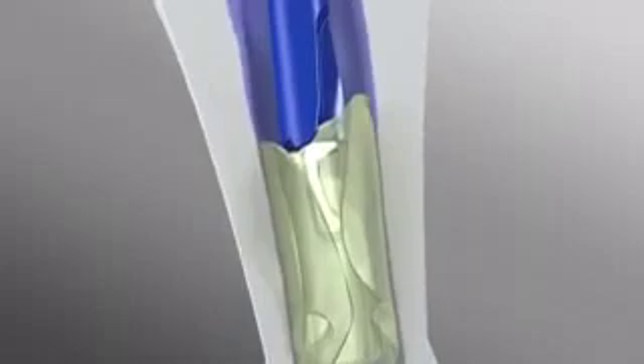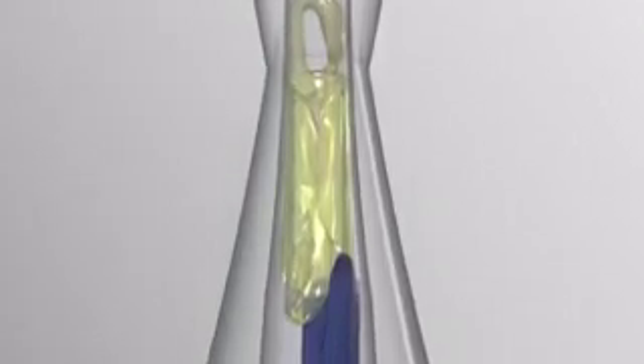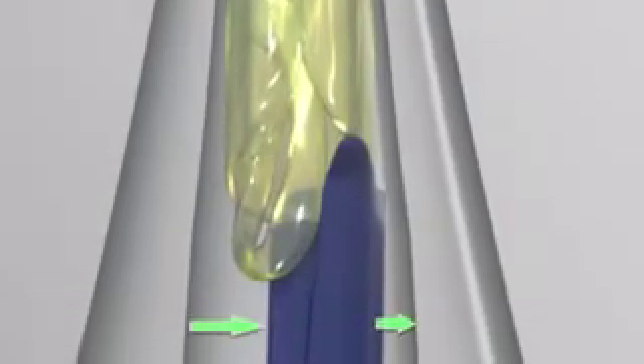Note the plunger tip is in contact with the trailing optic edge to ensure that the trailing haptic is folded in one of the normal orientations. Since a portion of the trailing haptic is always behind the optic and to the left, the plunger is pushed slightly to the right. All of this is normal. There is clearance on the left upper portion of the plunger to allow room for the folded haptic.